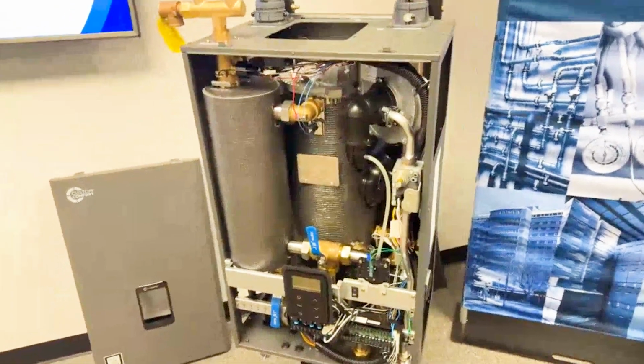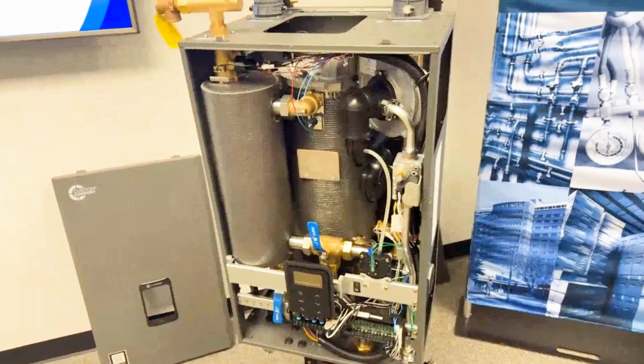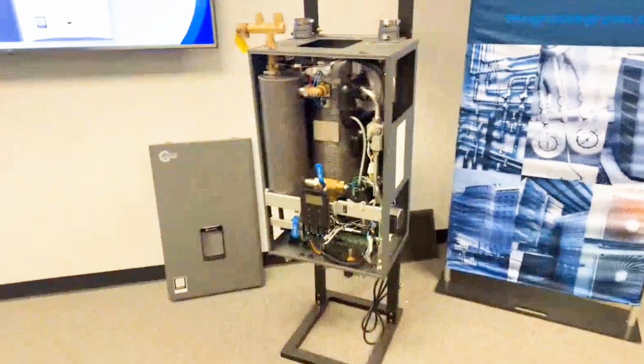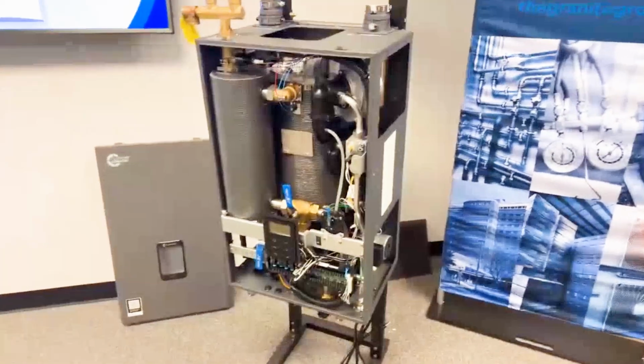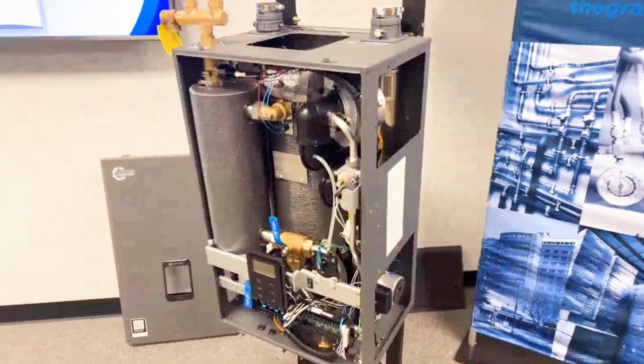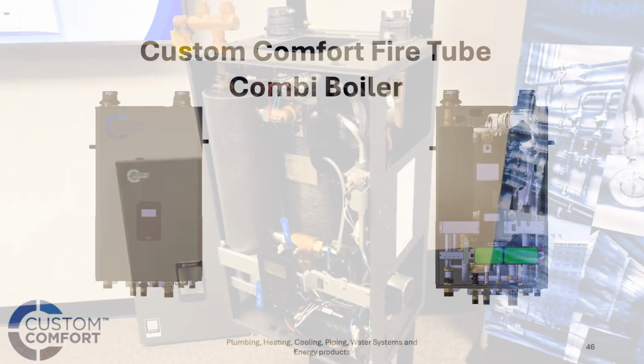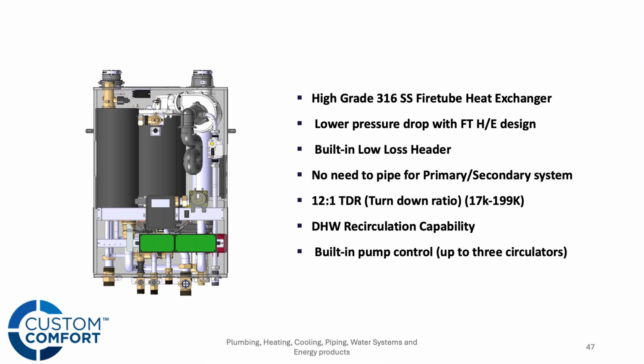So that is the Custom Comfort Fire Tube Combi. That's what we call this boiler. It's 199,000 BTUs of heat input and 199,000 BTUs of domestic input. On that boiler, we are using a totally different heat exchanger, right? This thing's got a 316 stainless steel fire tube heat exchanger, as well as a built-in low loss header and or buffer tank, whatever you want to call it. This is where we start to differentiate ourselves from other boilers in the market, is that low loss header and the buffer tank, and what we can do with it and the advantages that come with it. So with that being said, inside that low loss header is how we make our domestic hot water.